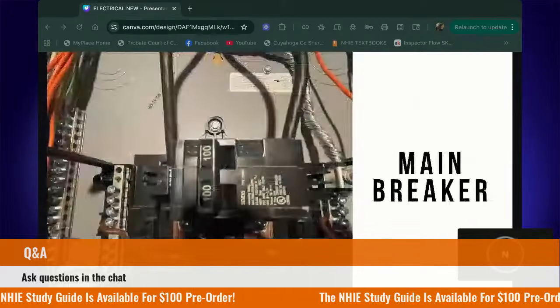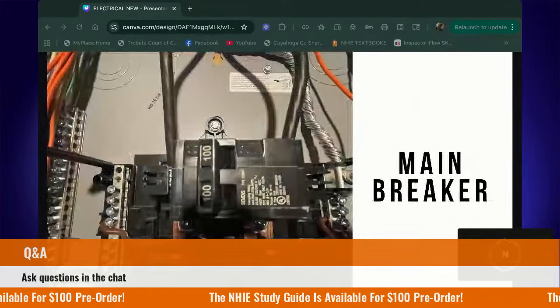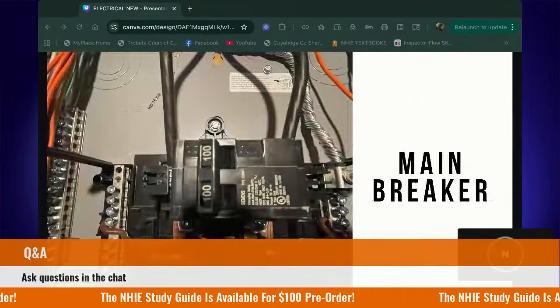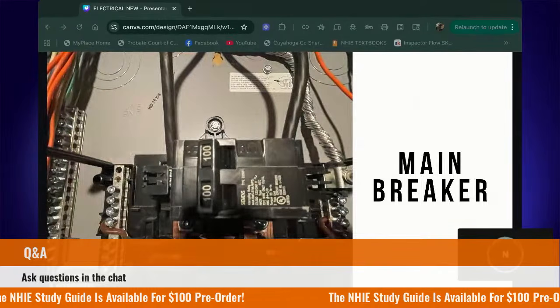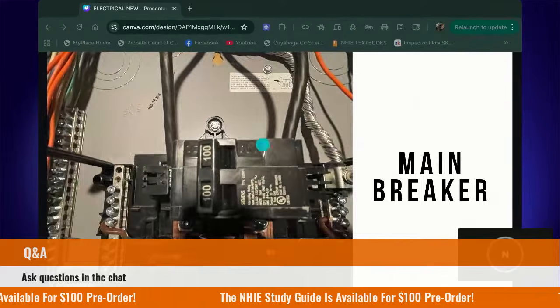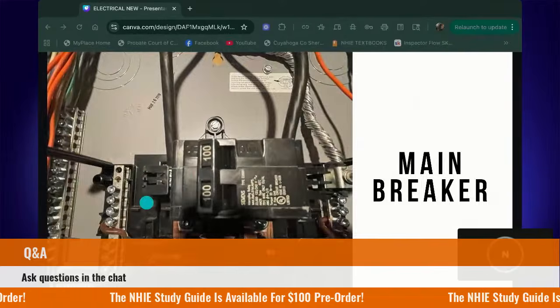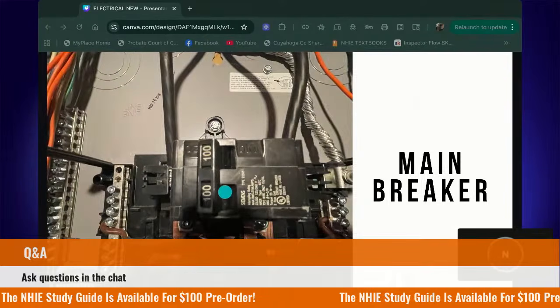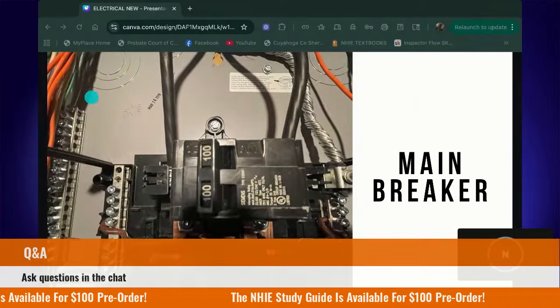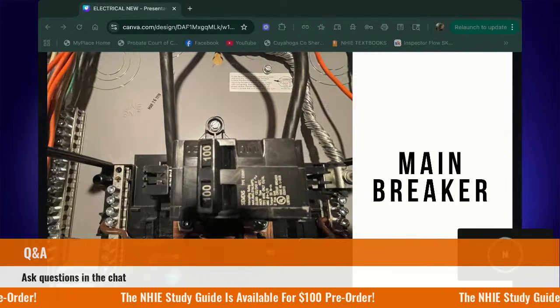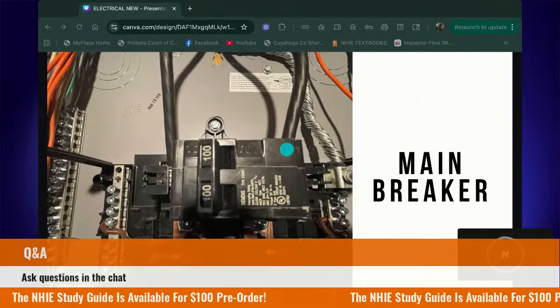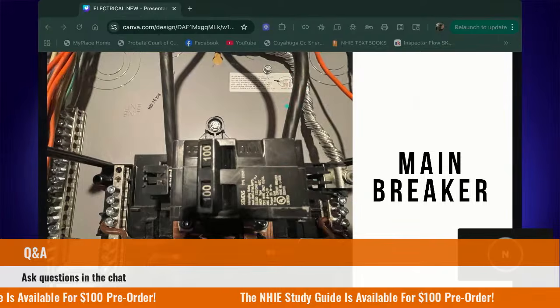Okay. And so then inside of our panel, we start at the top. We have our main breaker. This is the primary shutoff switch. So this, again, is akin to our main water shutoff. They also call it the service disconnect or main disconnect, whatever the case may be. But when you turn it off, you stop flow to all of your branch circuits that are in the panel.